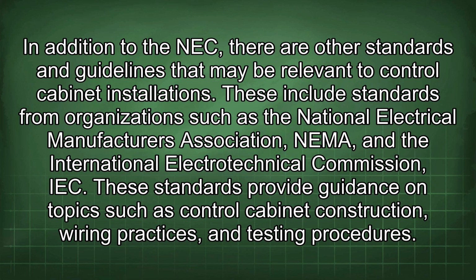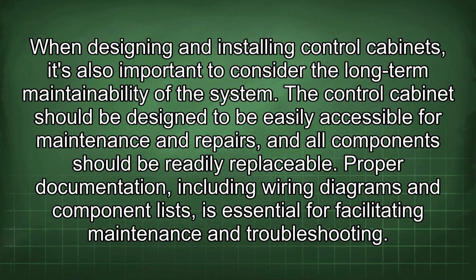In addition to the NEC, there are other standards and guidelines that may be relevant to control cabinet installations. These include standards from organizations such as the National Electrical Manufacturers Association (NEMA) and the International Electrotechnical Commission (IEC). These standards provide guidance on topics such as control cabinet construction, wiring practices, and testing procedures. When designing and installing control cabinets, it's also important to consider the long-term maintainability of the system. The control cabinet should be designed to be easily accessible for maintenance and repairs, and all components should be readily replaceable. Proper documentation, including wiring diagrams and component lists, is essential for facilitating maintenance and troubleshooting.